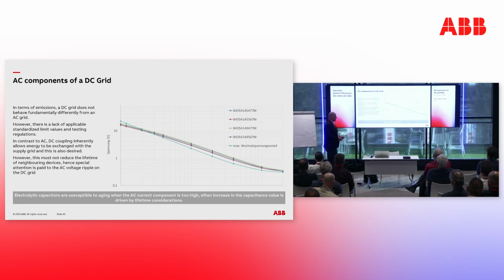So the first thing to check is whether the oscillations we've seen in the transient stability study are within the capacitor limit, and then do the same for the current, because otherwise the capacitors can age too fast. This is an important consideration for finalizing the system design.